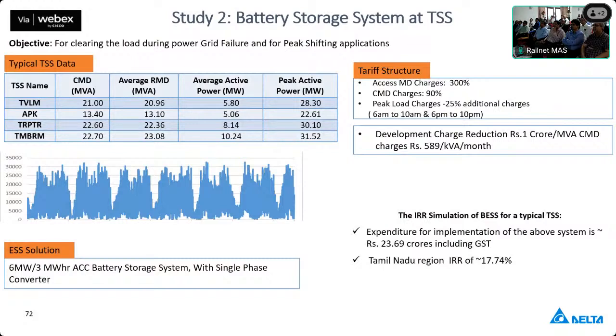You can see this is the Tambaram energy data what we have seen. There is a peak which goes up, and there is also a period where there is very less load. If we average it out, less than 50% is the average load that comes. So by looking at this graph itself, we can see there is a clear case wherein we can store energy at this period and discharge at the peak such that the maximum demand can be reduced.